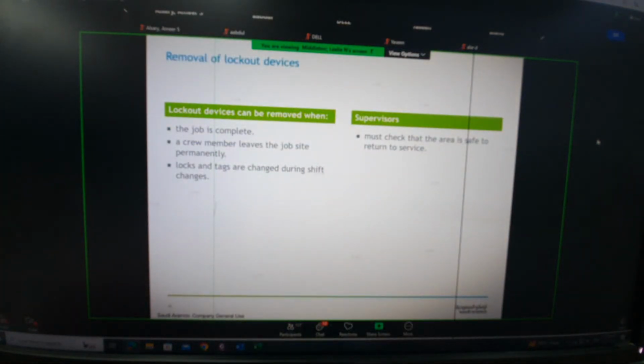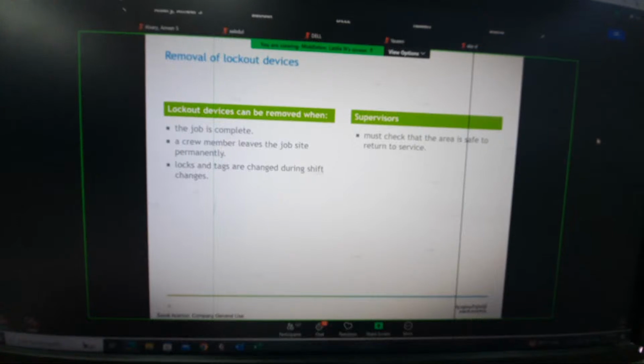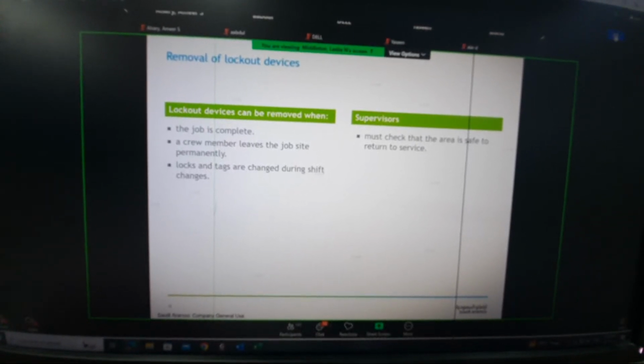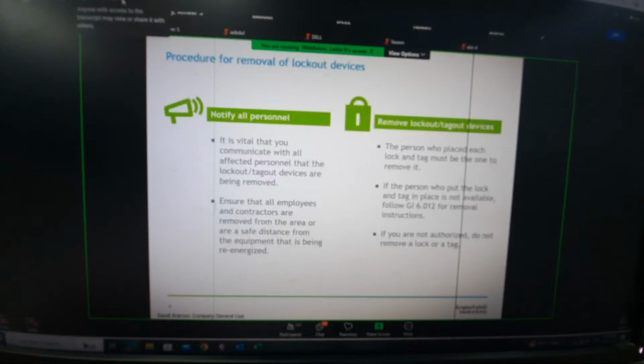So we'll just go through removal of lockout devices. A lockout device may be removed when the job is complete, or when a crew member completes his work or leaves the job site permanently. The supervisor must advise the operations supervisor that the work has been completed and that the locks and tags have been removed. Procedure for removal and re-energization of equipment: notify all personnel. It is vital that you communicate with all affected personnel that the lockout tagout devices are being removed.